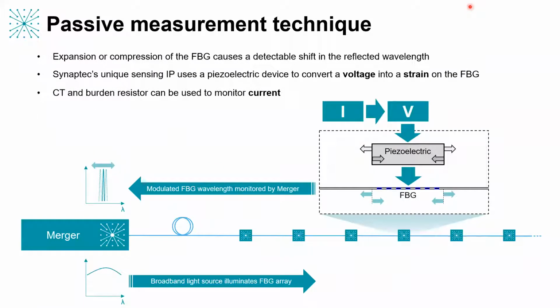So the interesting thing is, how do we then tune that to measure electrical parameters? And what we do there is we use a piezoelectric element. So as I'm sure most of you listening know, piezoelectric materials are those that expand and contract microscopically in response to an electric field within the structure. So fundamentally what our sensors are doing is they're taking a voltage or current that we want to measure, and they're converting that passively into an electric field aligned along a piezoelectric crystal. And that piezoelectric crystal is then microscopically expanding and contracting along the field line direction. And we are then measuring that expansion and contraction very, very accurately with our optical sensor.